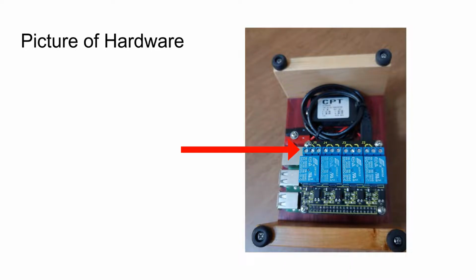Along the top of the board, there's a blue barrier strip. You can see the normally closed connector is to the left, the moving part in the middle, and the normally open connector to the right. The relays are numbered J5 through J2 in descending order along the top. Underneath the relays, there are LEDs that turn on when the relay turns on.